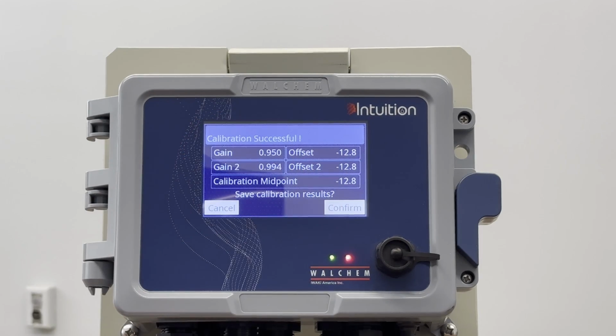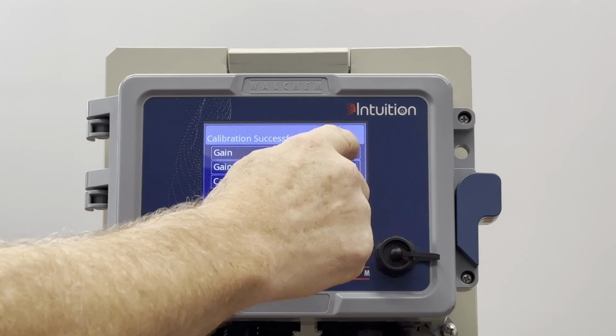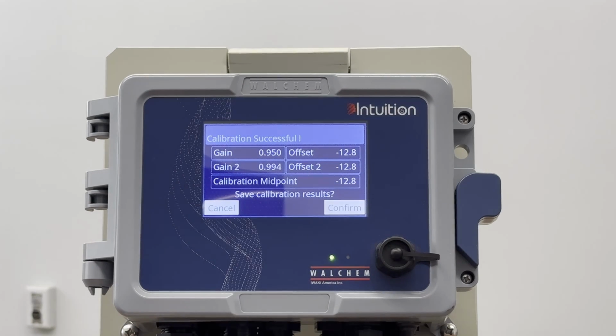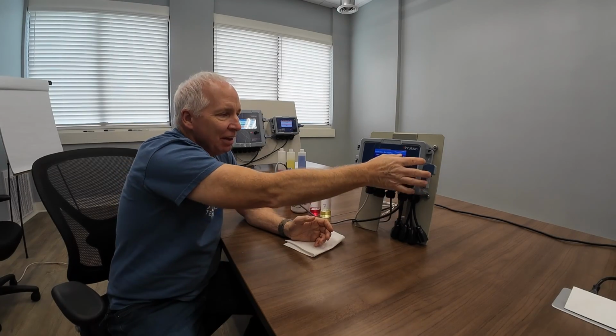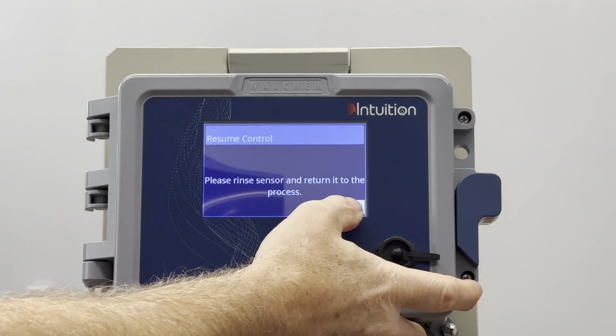And this is just what the controller is using to get a value, and it asks you if you want to save it. Well, as long as these are within, say, 0.8 to 1.1 over in here, and your offset's within plus or minus 30, I feel like it was a pretty good result and that the sensor's working properly. So I like this result. I'm going to hit confirm.